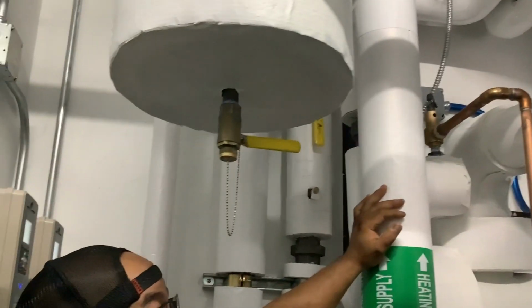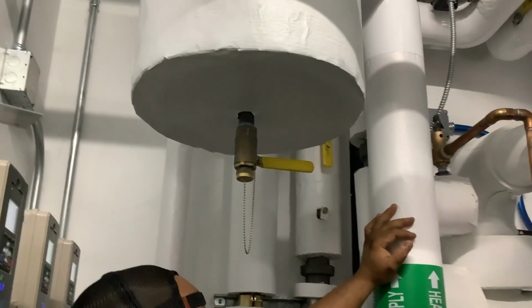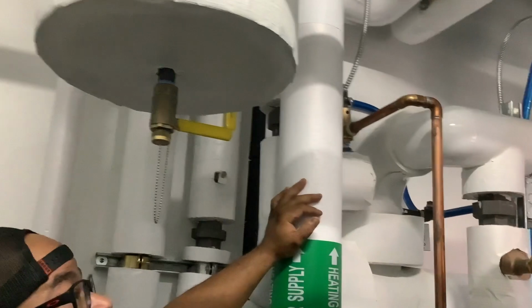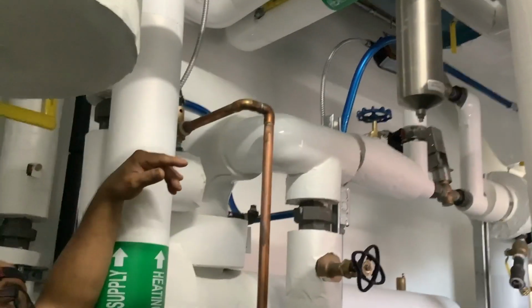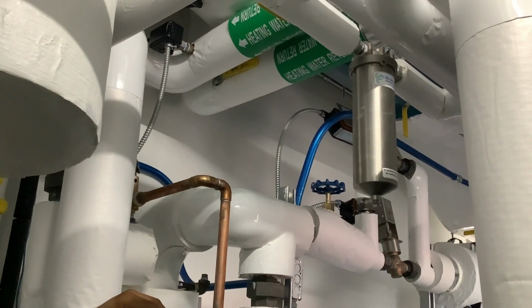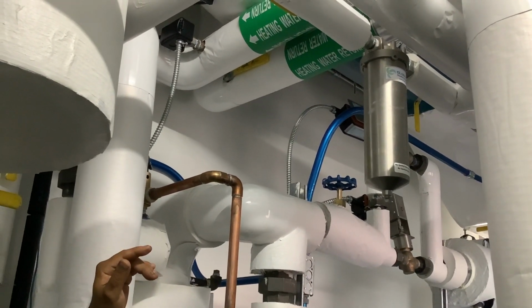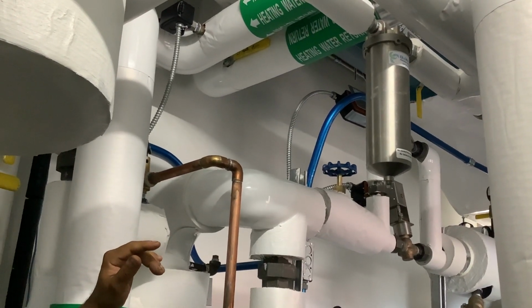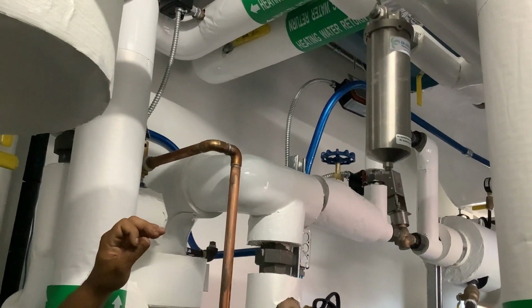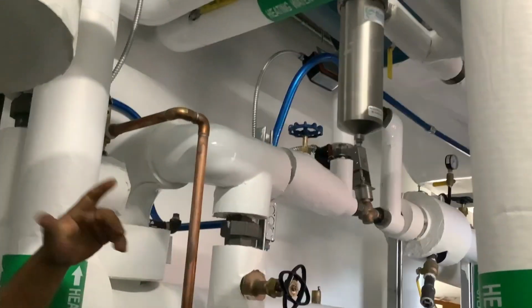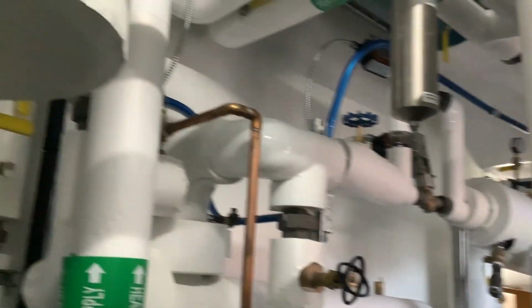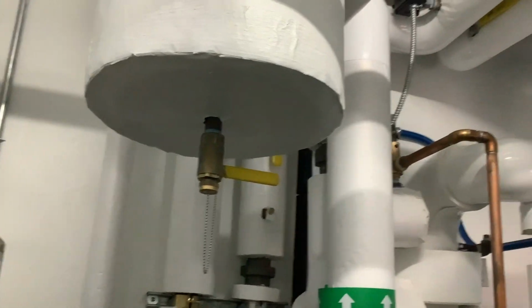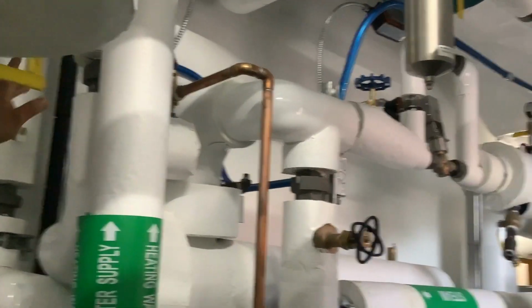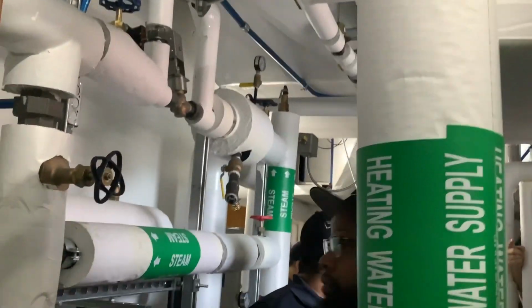Right above your head, you see that silver canister? That's a side stream filter. I don't know if you got those in other parts of the building, but that's one thing I really like about putting in new systems now. That cartridge filter gets a lot of the debris out. In the beginning you might want to check it at 6 months when it first starts, then once a year just replace the cartridges inside. If they look clean, it's fine, you don't need to replace them. Normally once you get the debris out, and as long as you're not introducing a bunch of new water, they don't need a ton of maintenance.